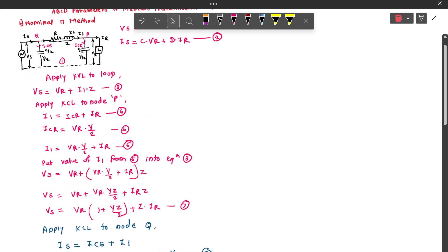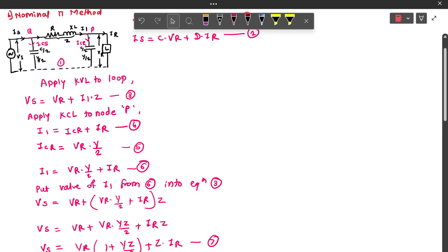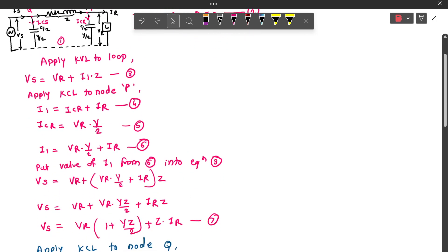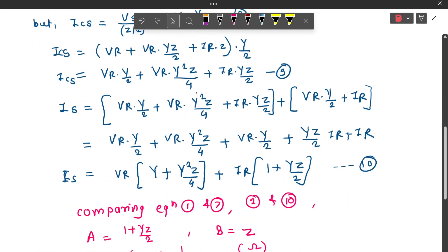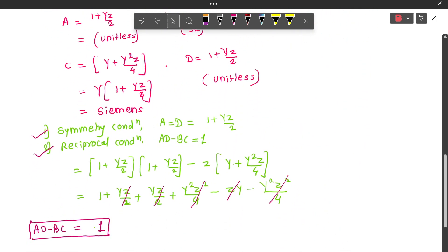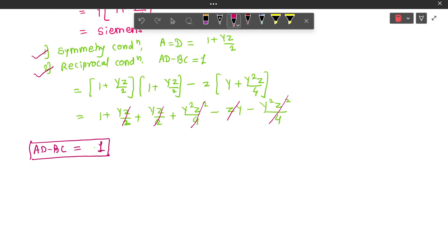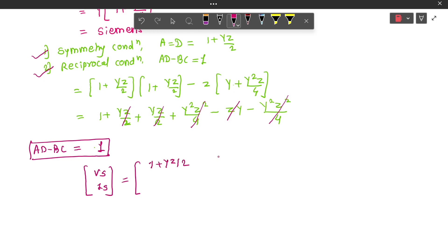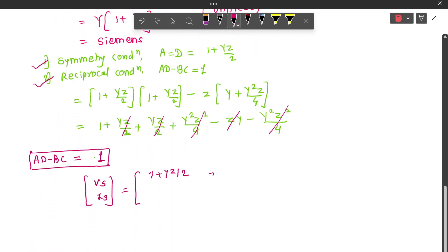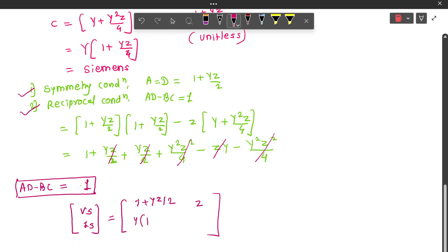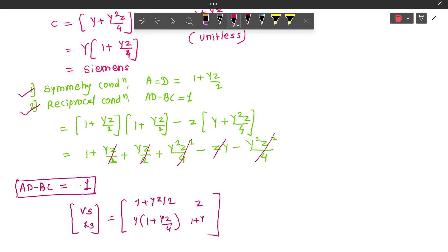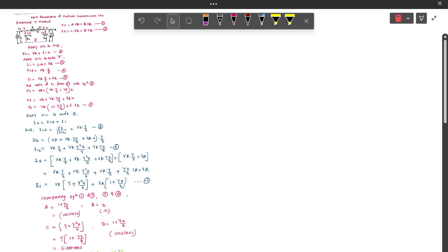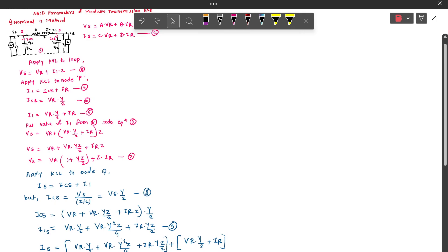By these expressions, we can determine the values of ABCD generalized constants of a medium transmission line using the nominal pi method. We wrote the standard expressions, derived VS and IS in a form comparable with standard expressions, and after comparing we obtained the ABCD values. The matrix form is: [VS; IS] equals [A=1+YZ/2, B=Z; C=Y(1+YZ/4), D=1+YZ/2] times [VR; IR]. Using this matrix, we can determine VS and IS to get performance parameters such as percentage regulation and percentage efficiency. Thank you.